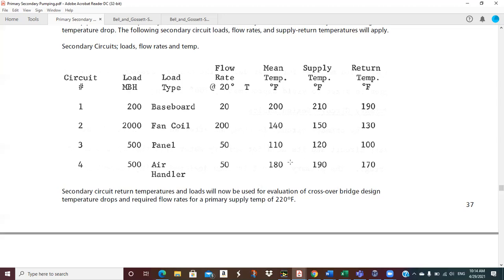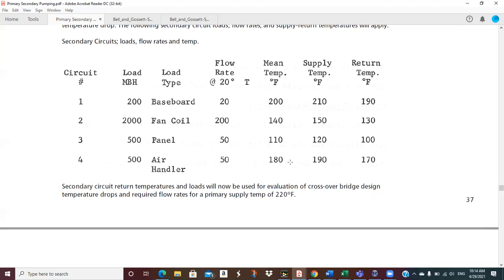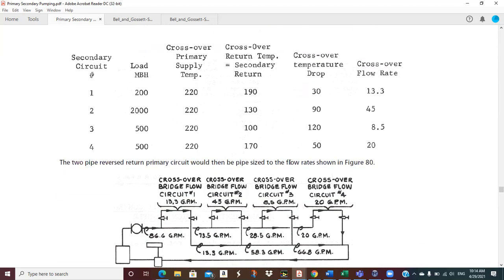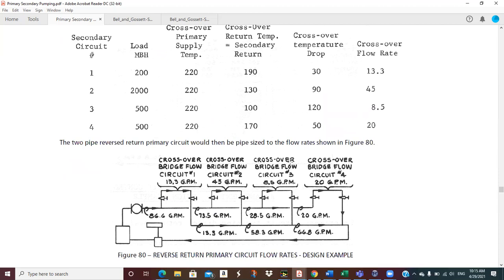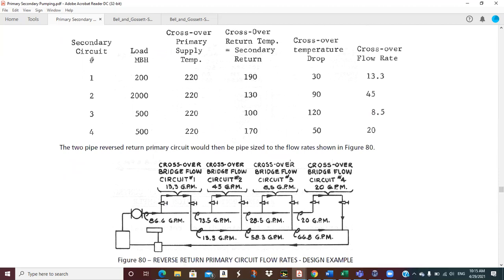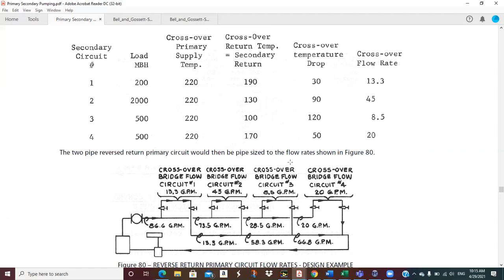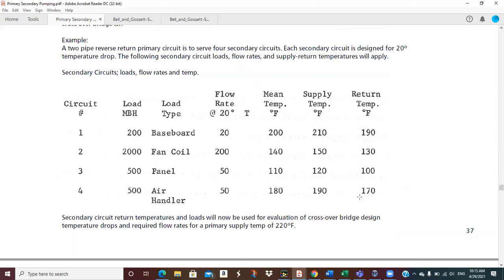Well, goodness gracious, 220. I've got my flow rates, I've got my loads. Gosh, this shouldn't be too hard to size everything up. Okay, let's take a look. I'm proposing a reverse return system. First of all, let's determine the required crossover flow rates. I know my supply temperature and I know my return temperatures, and these return temperatures just came from right here. That's just what I'm going to have based on what temperature water I want to put into my coils.